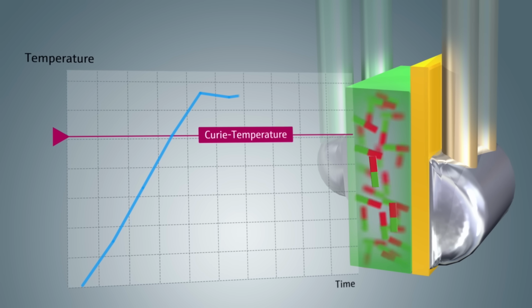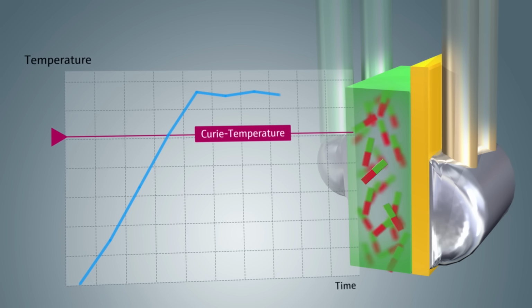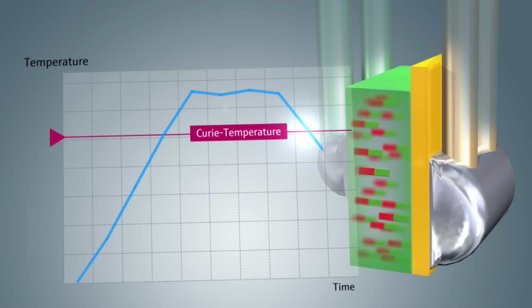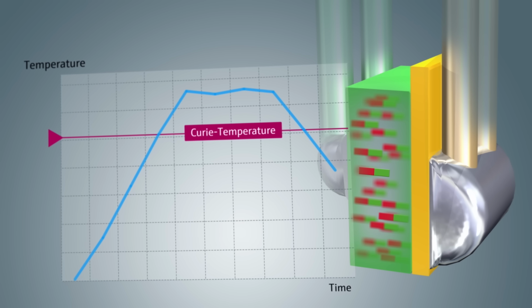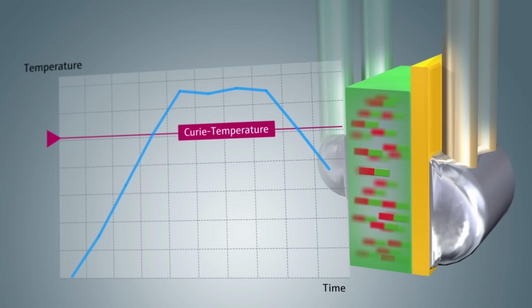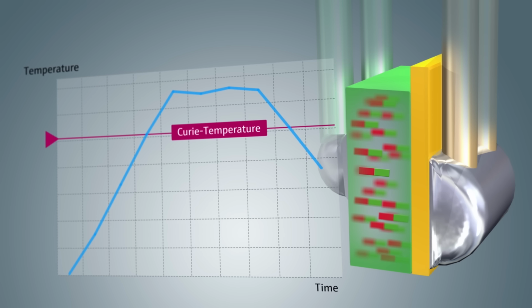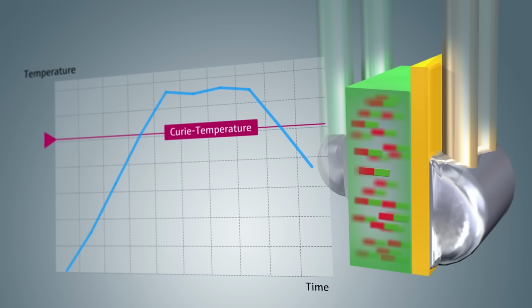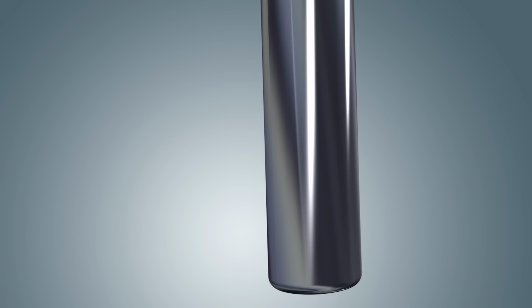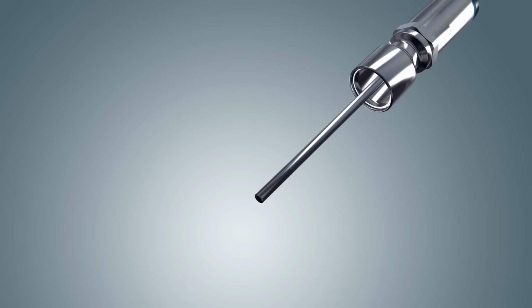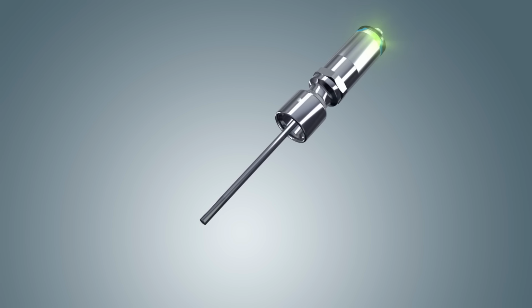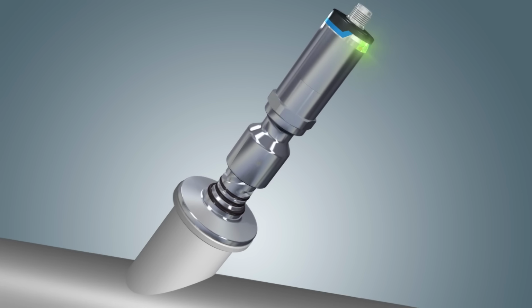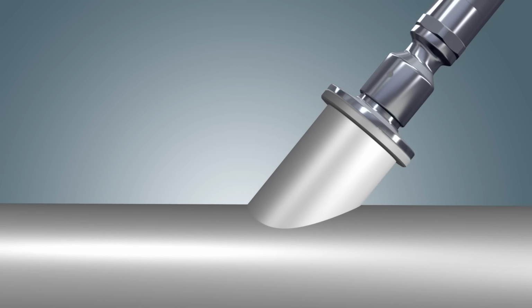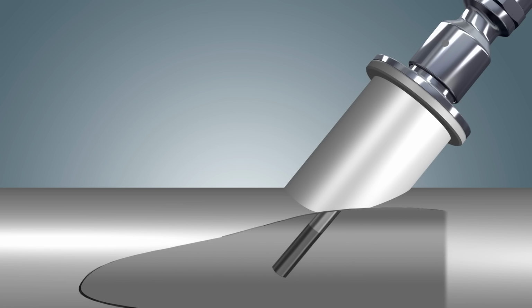This instant change in properties can be detected electrically, which enables the determination of the point at which the Curie temperature is reached. This temperature value is a material-specific constant that will not vary from its original determined value. The iTherm TrustSense uses this value in the form of a reference sensor consisting of such a material.